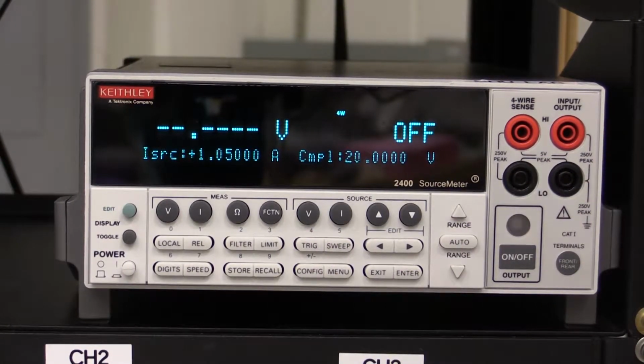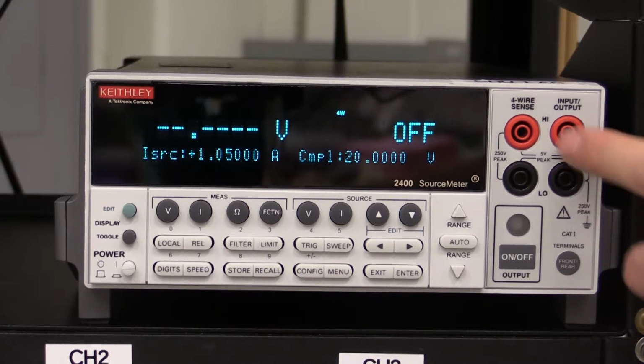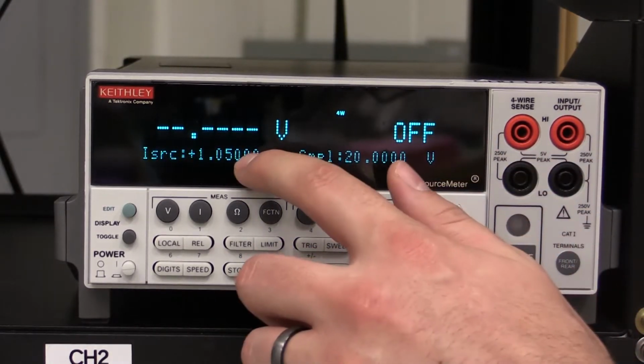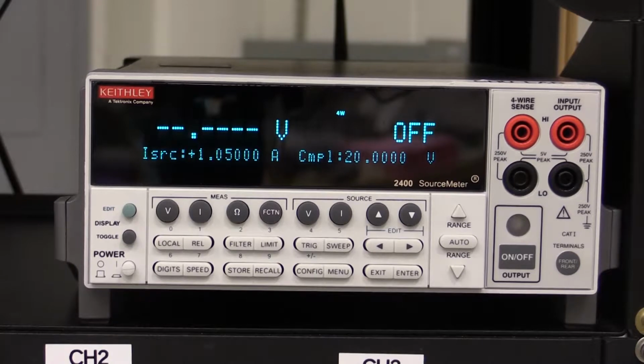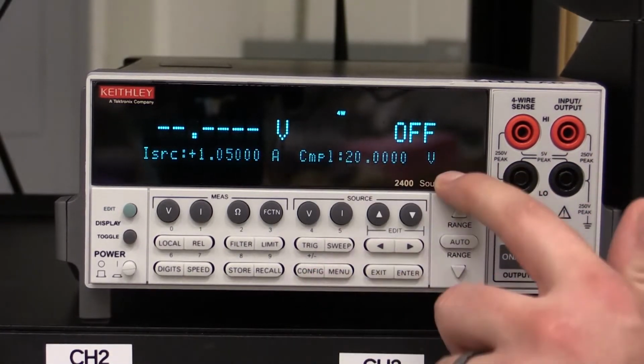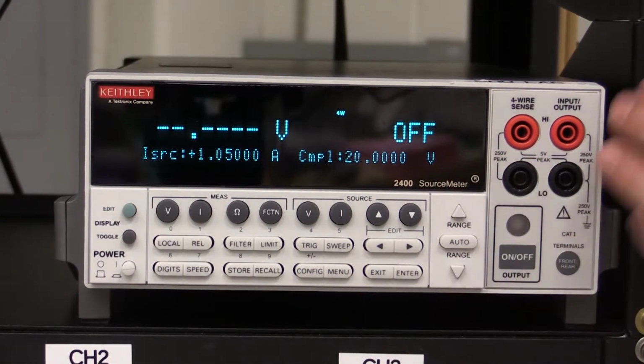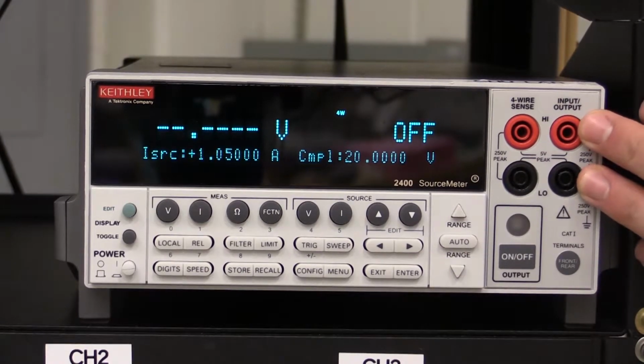This instrument will not exceed the compliance voltage. So in the example of hooking up a mega ohm resistor across these two leads and telling it to pump about an amp of current, you're basically asking it to put a megavolt across these two leads. But with the compliance voltage set at 20, it will not go beyond 20 volts across these two leads right here.